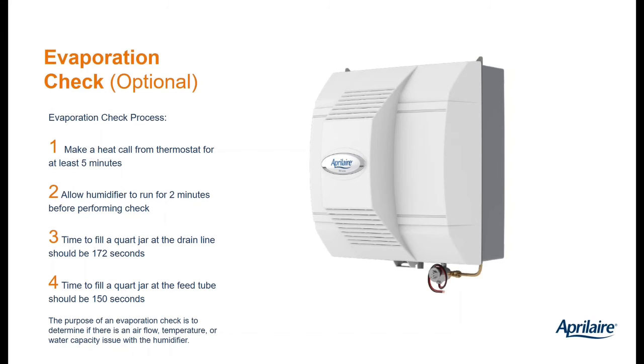If you think it through, you'll see that it should take longer to fill the quart jar from the drain line, because we should have been evaporating some water, so there's less water available. If you call us up with those two times, we can tell you how much water you're evaporating. But because quart jars are certainly not calibrated devices and you can be off by a few seconds, use the general guideline that we show you there. You can always give us a call and we can help you out.